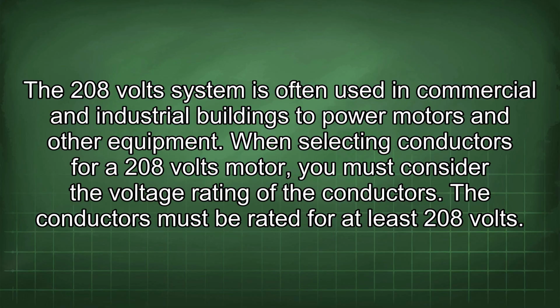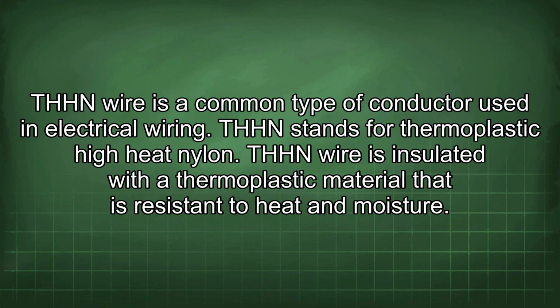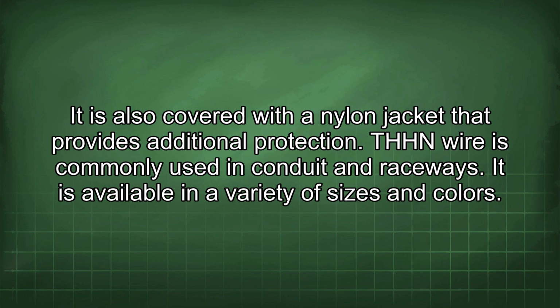When selecting conductors for a 208 volts motor, you must consider the voltage rating of the conductors. The conductors must be rated for at least 208 volts. THHN wire is a common type of conductor used in electrical wiring. THHN stands for thermoplastic high heat nylon. THHN wire is insulated with a thermoplastic material that is resistant to heat and moisture. It is also covered with a nylon jacket that provides additional protection.